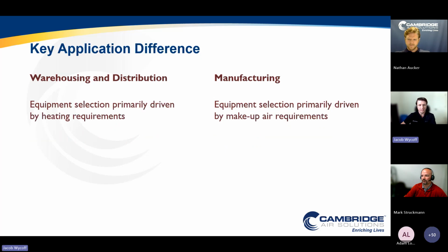And how does this play out in the way that we look at the HVAC system for these spaces? So with warehousing and distribution, we're primarily going to be looking at what's the best way to heat this space. We're going to optimize our equipment selection around heating the space efficiently and effectively. And then after doing so, we're going to make sure that we're meeting the ventilation requirements required by code for that space. Whereas with manufacturing, we're going to first look to cover all of the makeup air requirements of the space to be able to make up any exhausted air, control room pressure, things of that nature. And then after we have our equipment selected and optimized around that, we're going to make sure that we are able to meet the heat load of the space somehow.